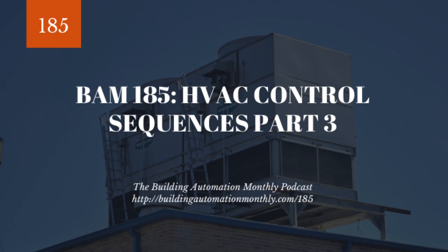So a single path air handler, constant volume, is going to have fan safeties, just like an actual air handler VAV. And this throws a lot of people, because people are like, why do we have high static and low static for a fan if it's a constant volume fan? Well, that's because downstream effects on that system can affect the fan and cause overpressurization or underpressurization issues. Overpressurization is where there's some form of blockage, maybe from smoke dampers, or maybe someone commanded all the constant air volume VAVs closed or something.